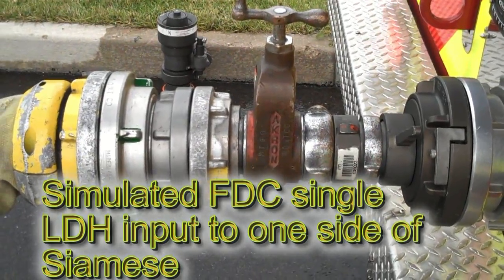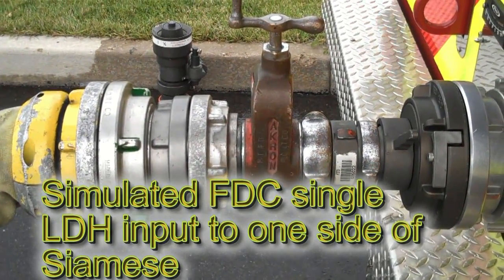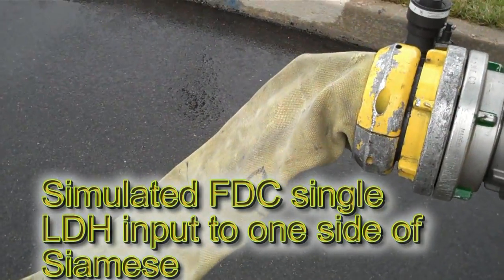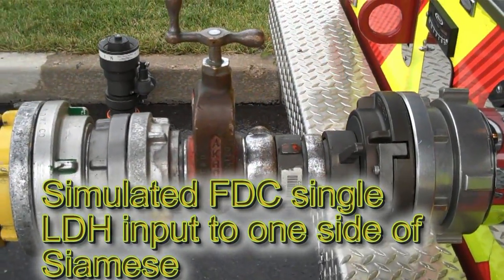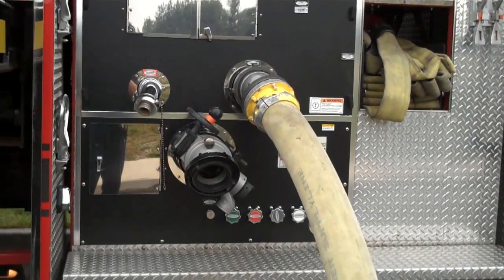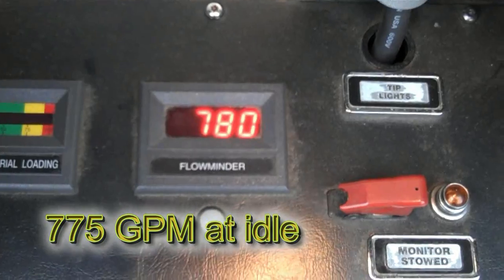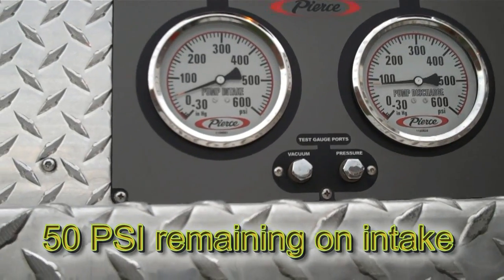The next section of the video will be dedicated to further proving that the five inch single siamese input will not restrict our flow for sprinkler systems. As you can see, we've got a five inch LDH supplying what is our simulated FDC — this is the FDC side from our LDH discharge to our adapter set simulating the FDC input on one side. The Flowminder reads roughly 775 gallons a minute and we're at roughly 50 psi intake.